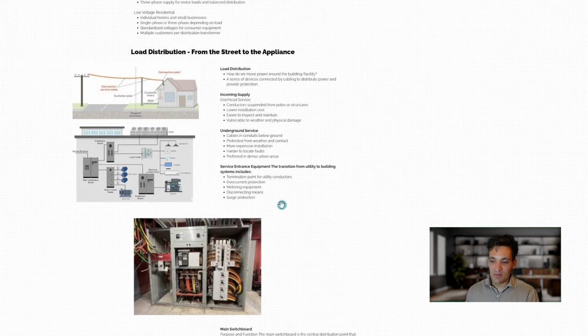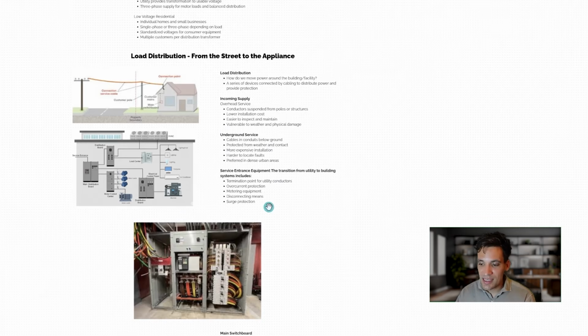There would then generally be a single piece of equipment which has the service entrance equipment. So this might be, on a building, the main switchboard, or on a residential or small load, your house's distribution board. This piece of equipment will be the termination point for the utility connection. It will also probably have some sort of fuse or circuit breaker, and it will also have your metering equipment. So this is where you measure how much power you're being provided, and there might also be surge protection.